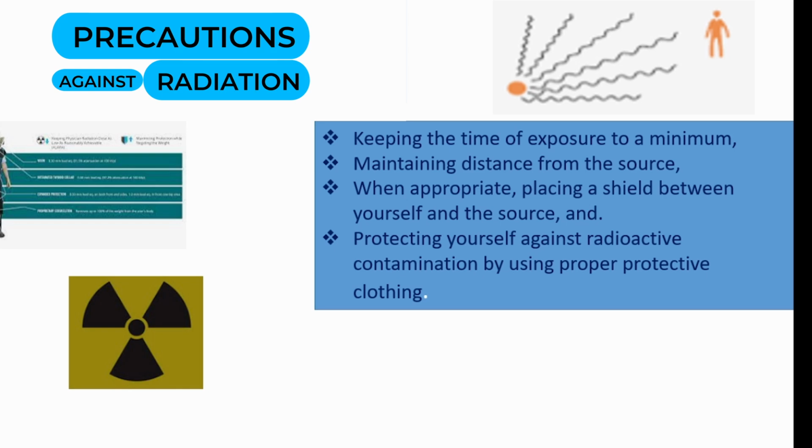When you go to the radiology department, you are going to see different types of shields which can be used. At the control panel, where the person exposing is with the controls, there is a panel that is also used to shield against radiation. The doors and the walls of a radiology building are also coated with a thin layer of lead that can be used to absorb part of the radiation so that we minimize radiation transmission to unnecessary targets.